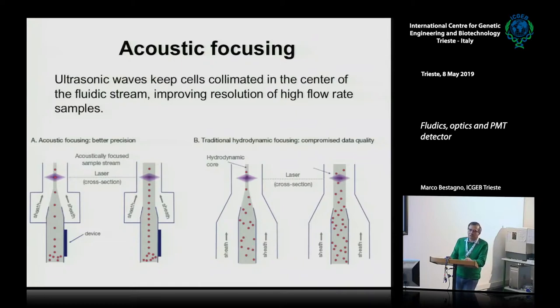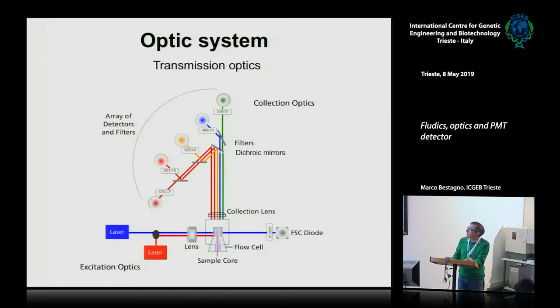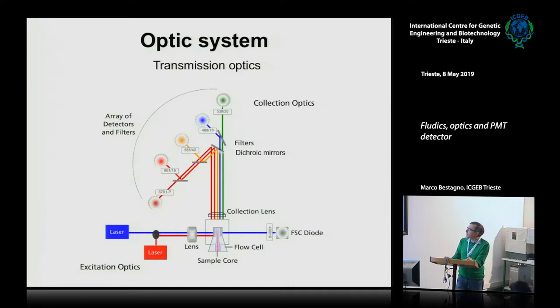Now we move to the optic subsystem, which includes first of all the lasers — they can be lasers of different wavelengths for the excitation light. There are lenses that collimate the laser beam into the flow cell, and a number of collection lenses, dichroic mirrors, and filters to split the light into different wavelengths.